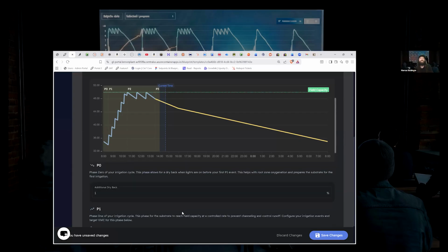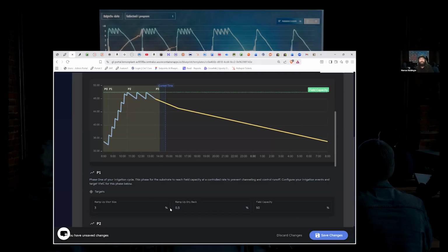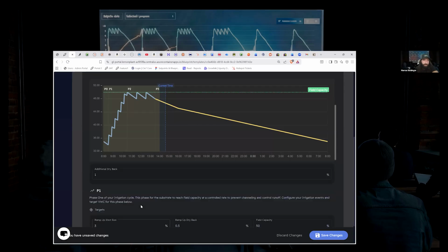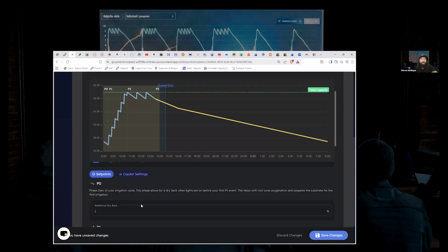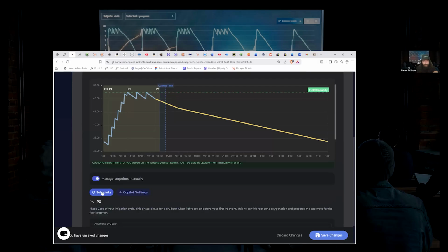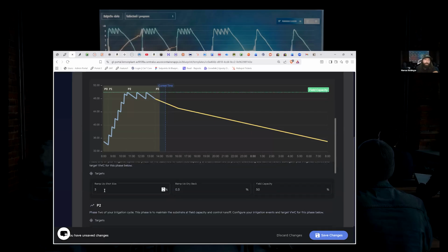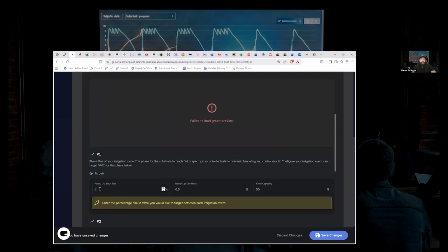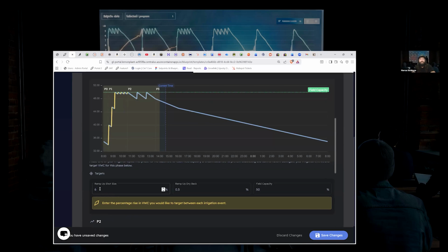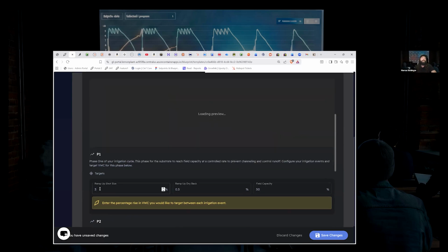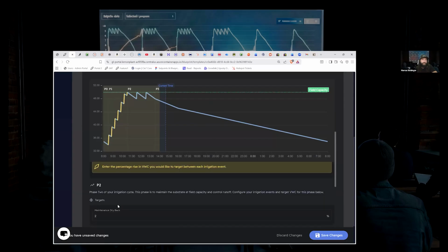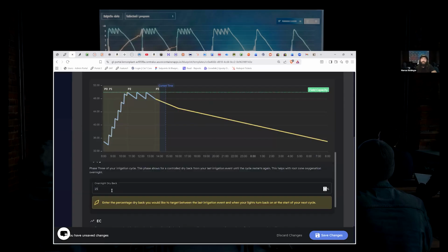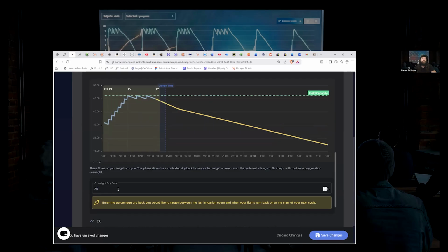But for right here, where we're talking about blueprints, we really only need to see what those target values are going to be and how we want to schedule those either week by week or day by day, depending on how intricate you want to go with it. But basically, we got two tabs. You got set points where we can set in what we want our target values to be, same interactive graph. Although this time it's pretty cool. I'm really happy about this. Whenever you make a change, it is immediate. There is no delay, there is no clicking in a box and waiting for it to take forever to update. For example, I came in, I want to change my overnight dryback from 15 to 30. It's just immediate.